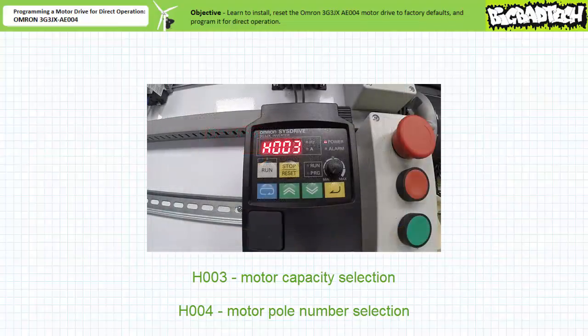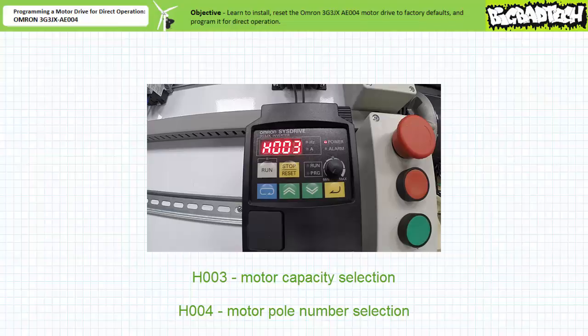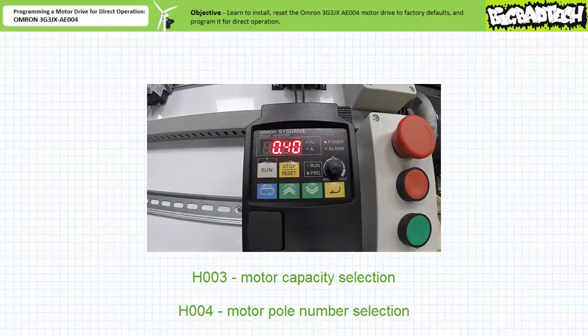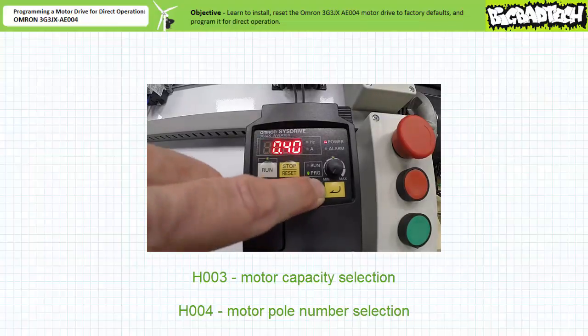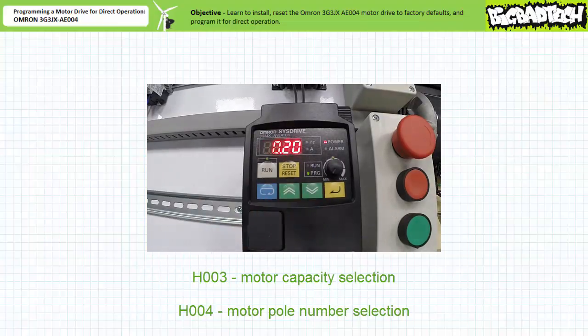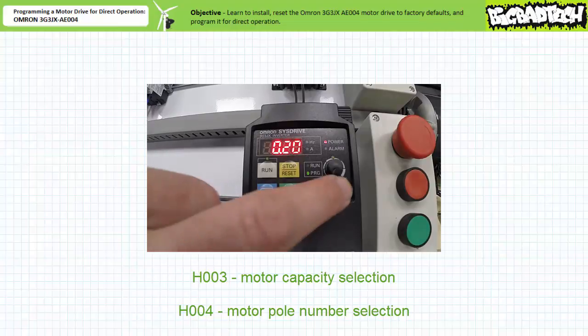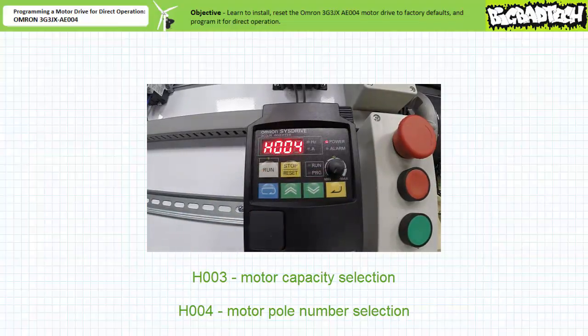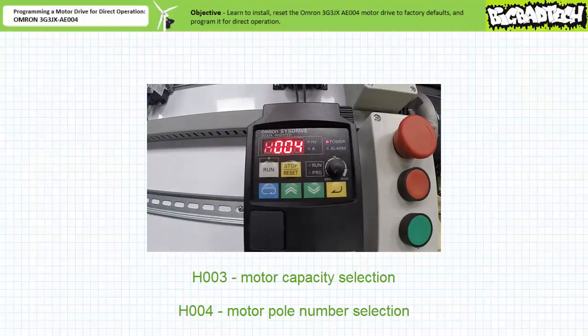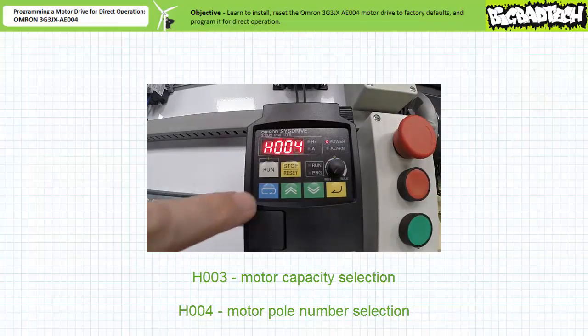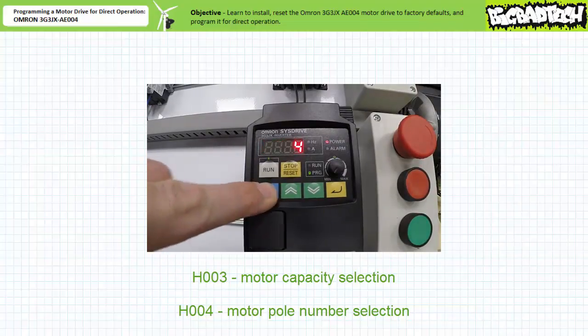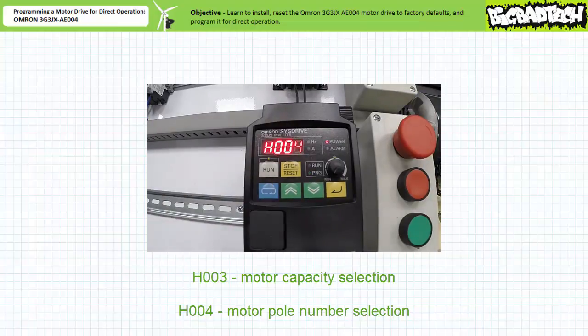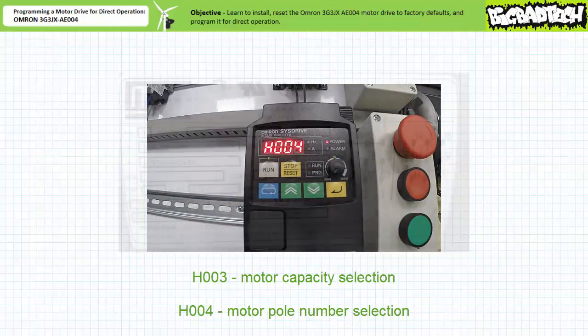Navigating to the parameter H003 motor capacity, we find the entry at the factory default of 0.4 kilowatts or 400 watts. One decrements to 0.2 kilowatts or 200 watts and presses enter to save this value. Navigating to parameter H004 motor pole number selection, we find the entry at the factory default 4. This matches our given motor, so no change is warranted.